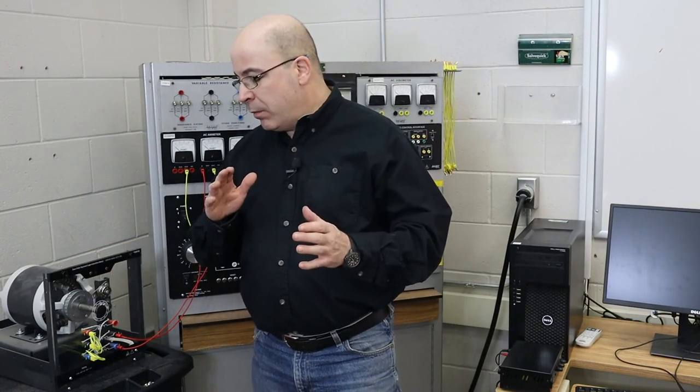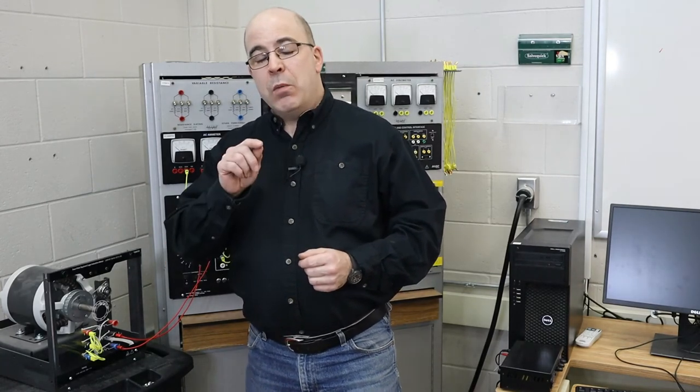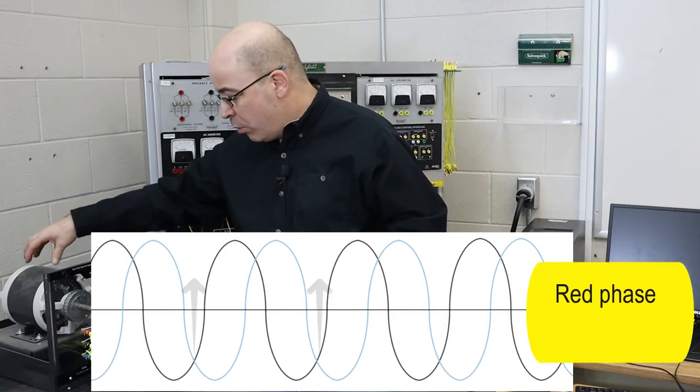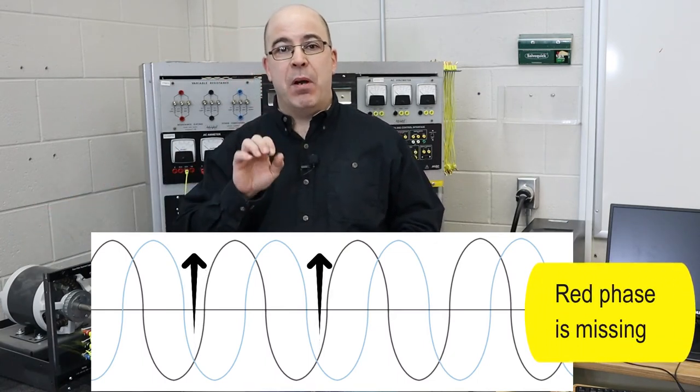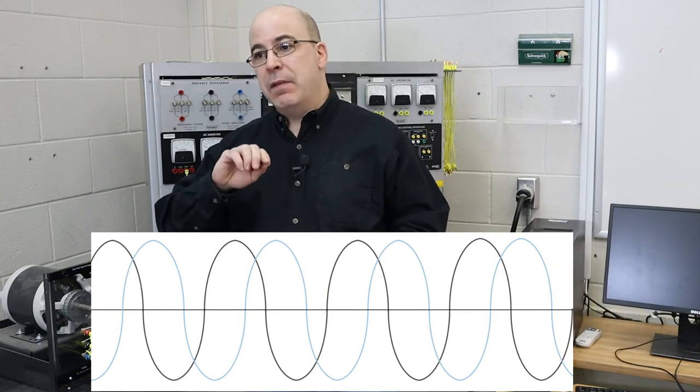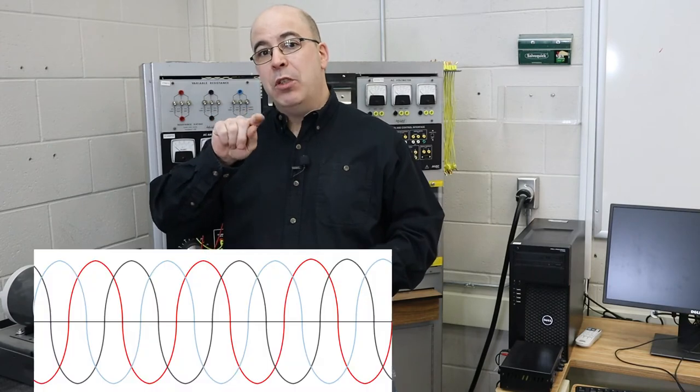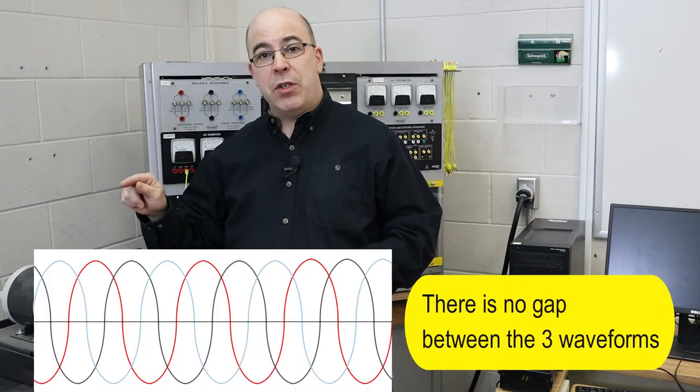Well it comes down to how the voltage waveforms interact. We've lost one phase. Now for the three phases what happens is that there's a gap in the sine waves and the rotor basically sees this as a pulse. Because of the fact we do not have a complete three waveforms that helps establish a direction of rotation.